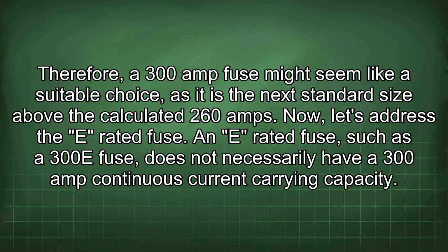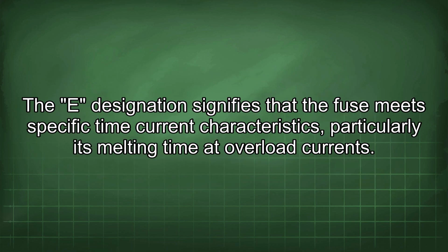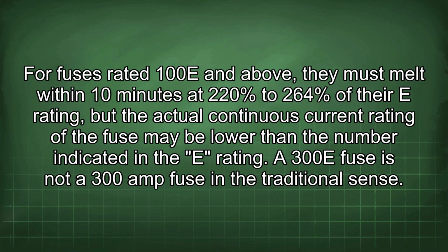Now let's address the E-rated fuse. An E-rated fuse, such as a 300E fuse, does not necessarily have a 300 amp continuous current carrying capacity. The E designation signifies that the fuse meets specific time current characteristics, particularly its melting time at overload currents. For fuses rated 100E and above, they must melt within 10 minutes at 220% to 264% of their E rating, but the actual continuous current rating of the fuse may be lower than the number indicated in the E rating.